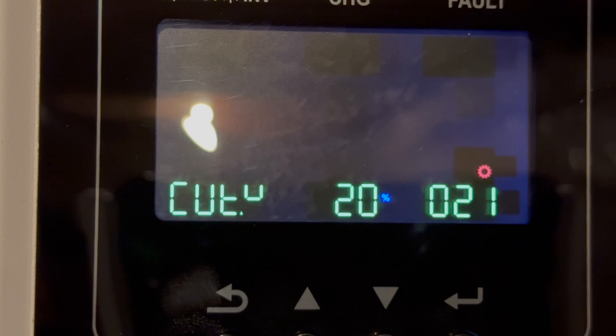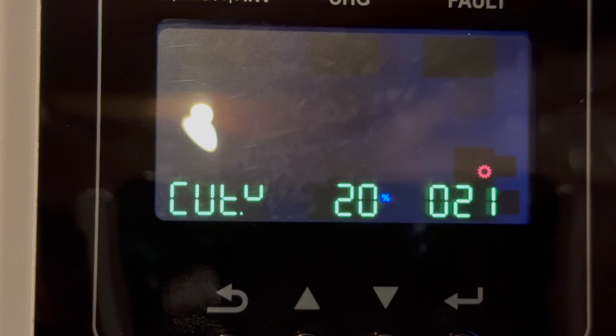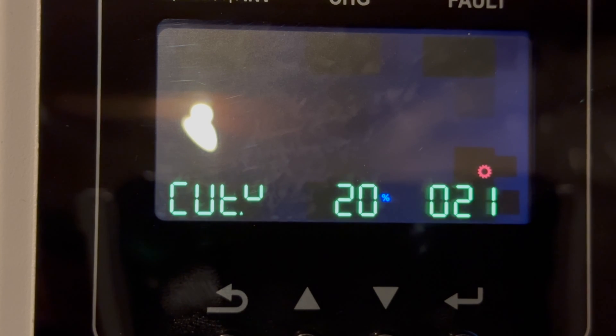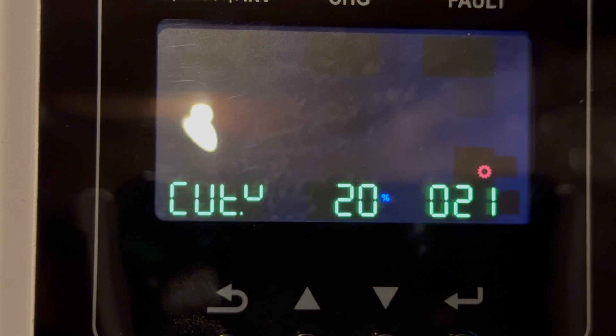Setting 21 is the emergency cutoff charge of the batteries, which will force the inverters to charge the battery and push everything to bypass line mode so that the grid will support the loads. If there is no grid, it will try to default to solar. If there is no solar, then it will just shut down.